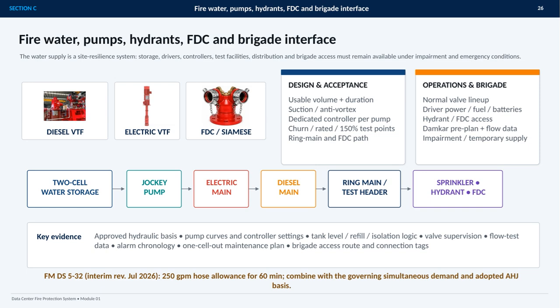Design and acceptance should confirm usable volume and duration, suction conditions, dedicated pump controllers, churn, rated, and 150% test points, along with the ring main and FDC path. Operations are equally important. The normal valve lineup, fuel and battery readiness, hydrant and FDC access, pre-planned brigade information, and temporary supply arrangements must be understood before an incident occurs.